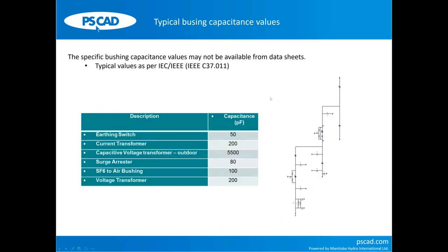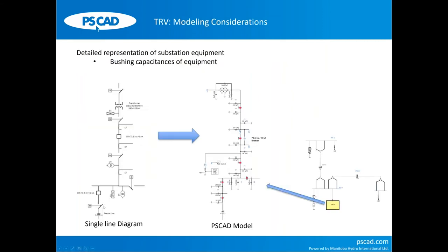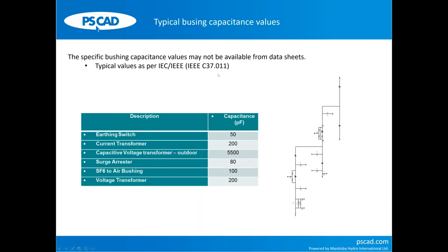So the challenging part is defining all these stray capacitances, because it's not easy to find those values. As you say, you get the SLD diagrams from your client or your substation design department, but not necessarily are they providing you any of the stray capacitance information.